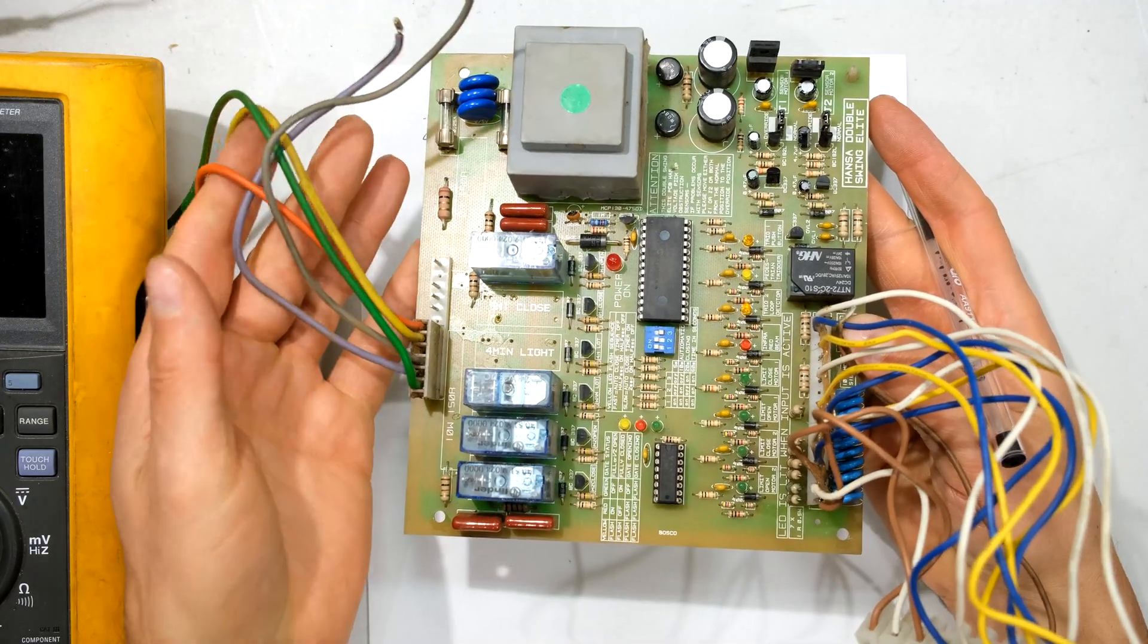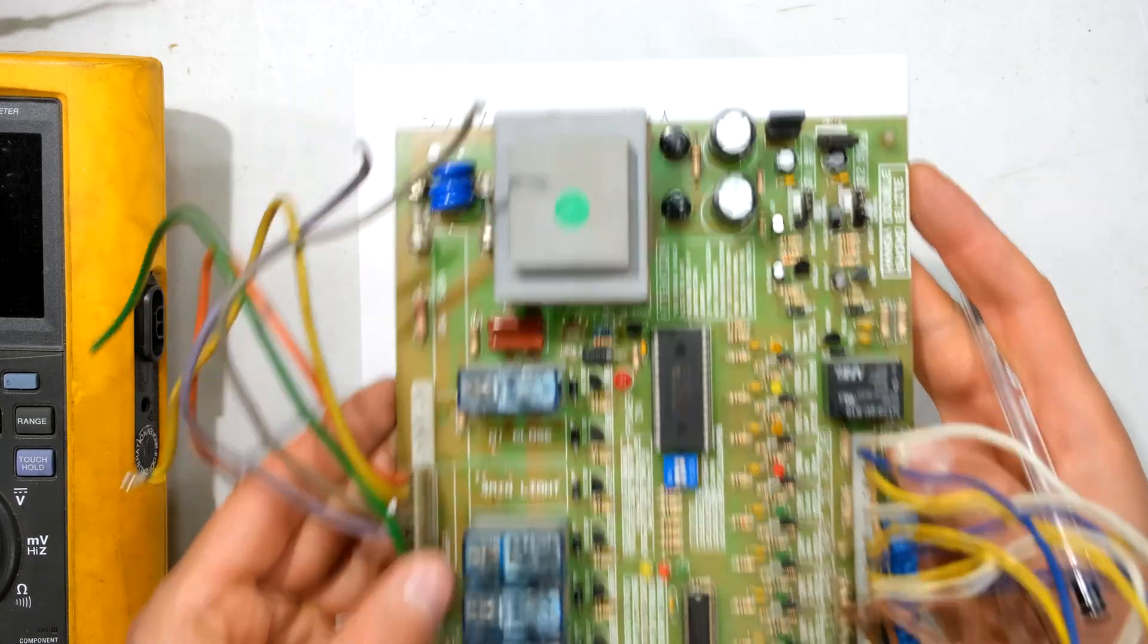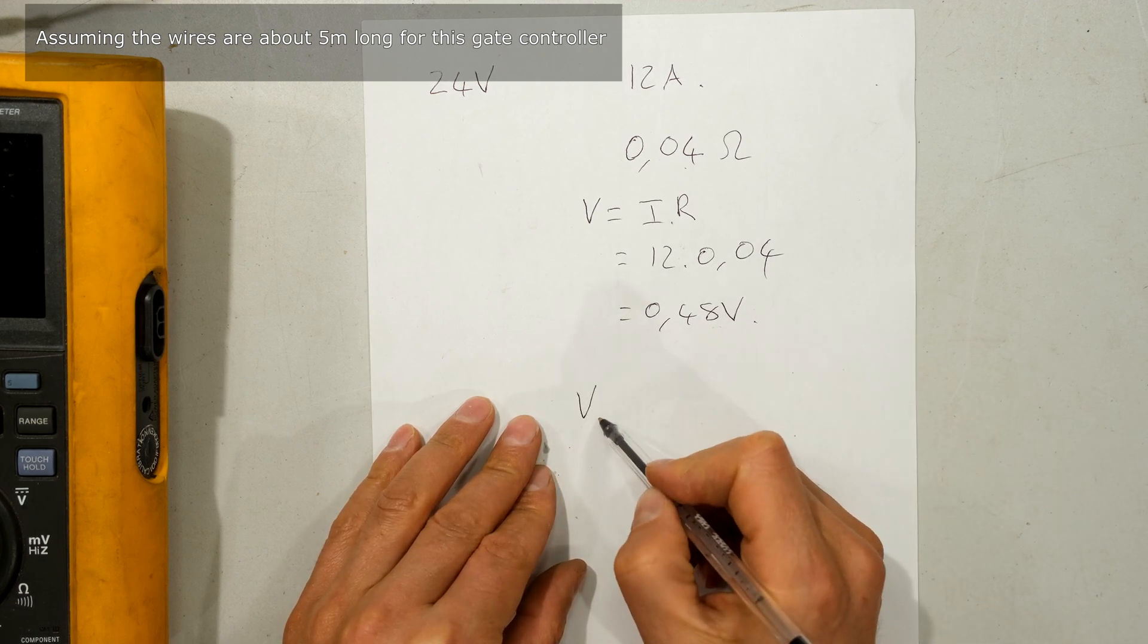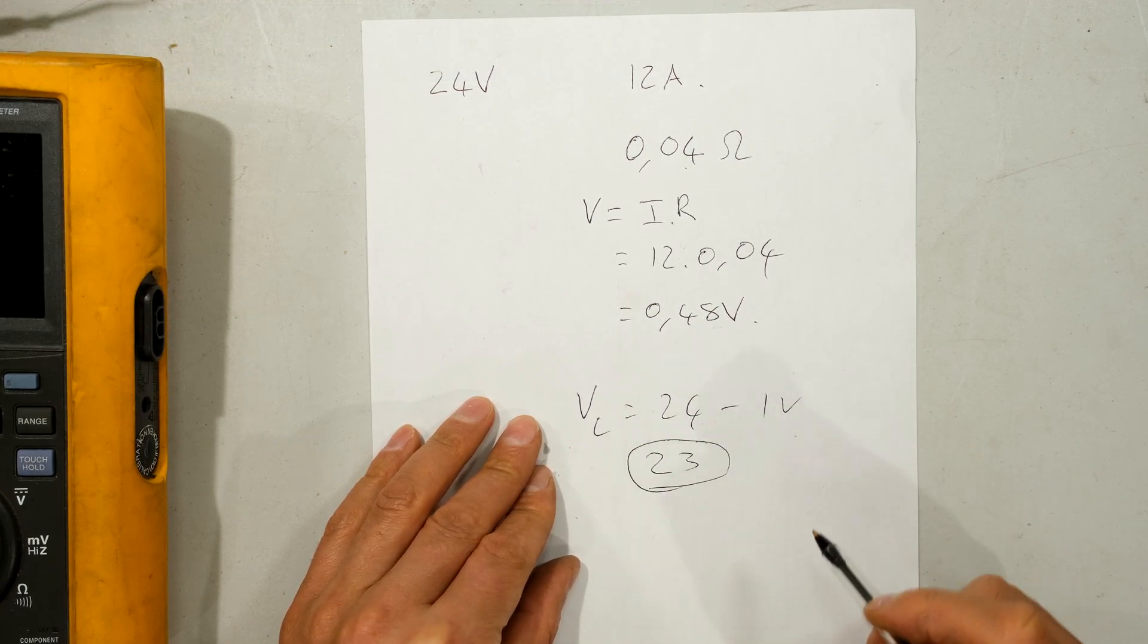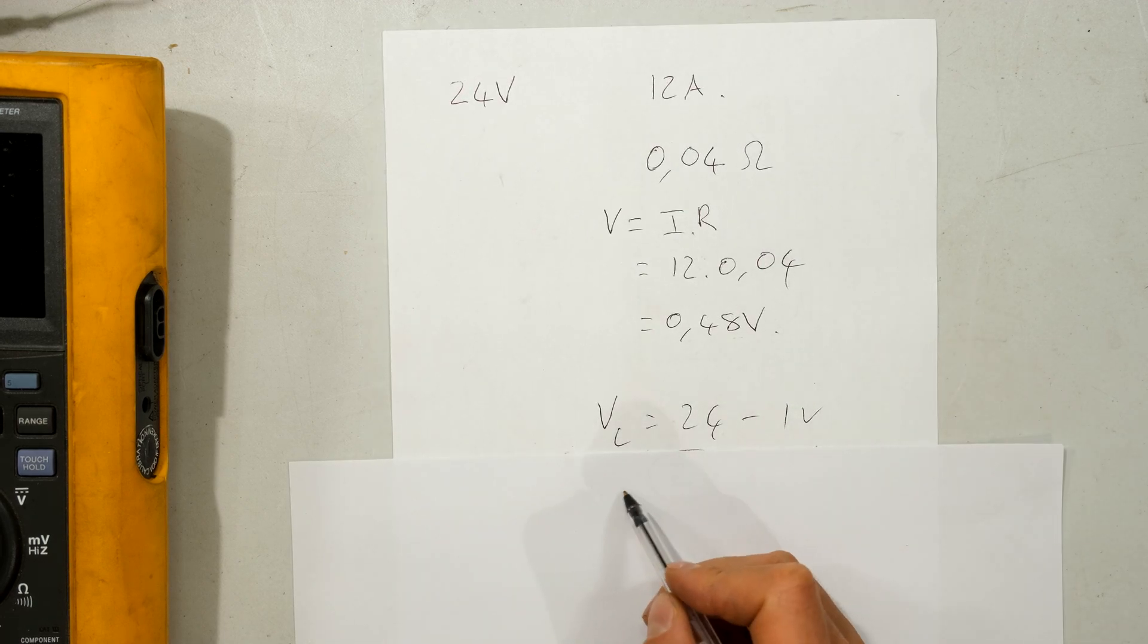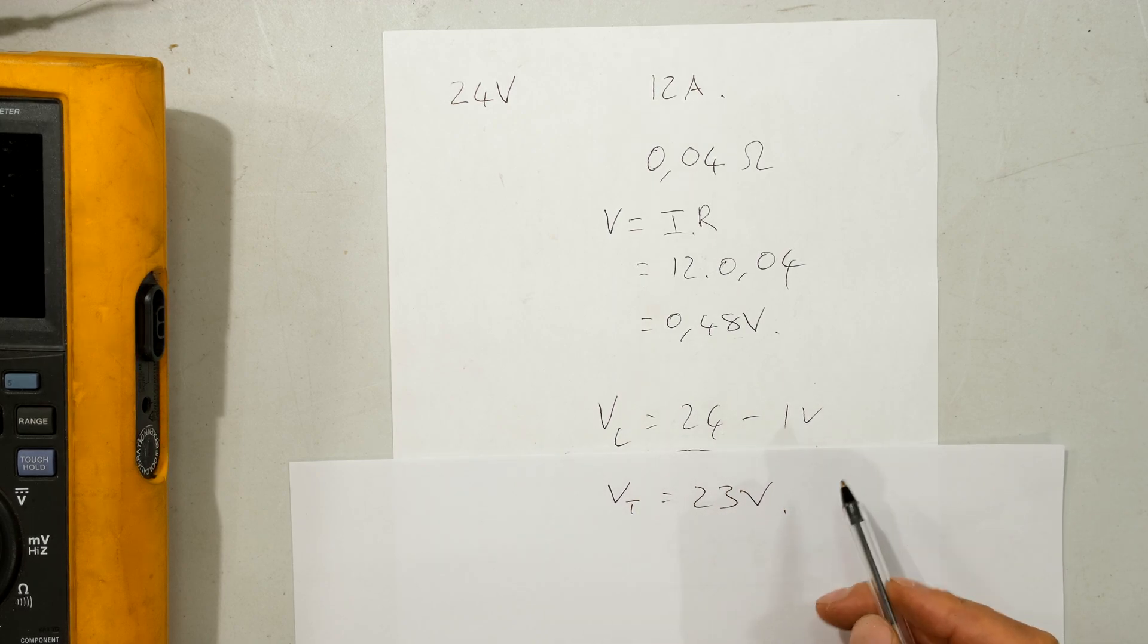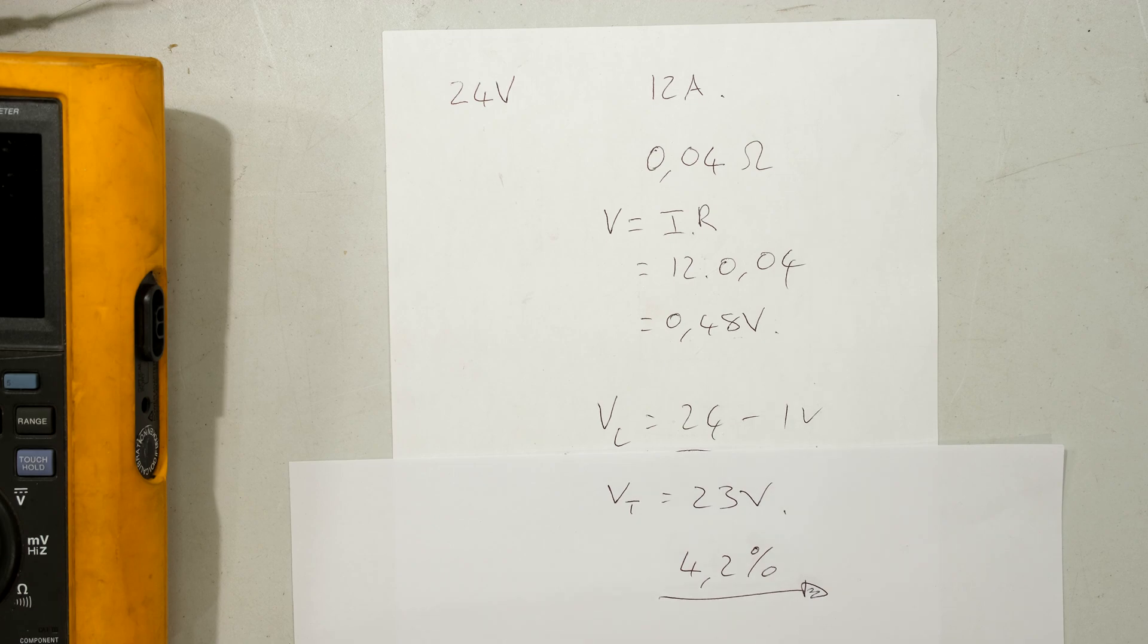Now all these wires also have resistance, so we have to factor in the resistance of the actual wire itself. So let's just assume the volt drop of the wires is also about 0.4 volts. That means the losses is 24 minus 1 volt. We've lost one whole volt just to do with the wire and the contacts. So if our contact and lead loss was one volt, that would leave us with a total voltage of only 23 volts. And if you work out the losses, you're going to get a 4.2% loss just to do with contact and lead resistance.